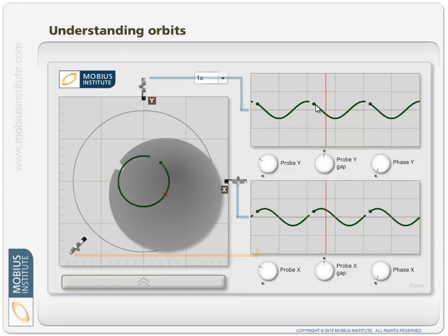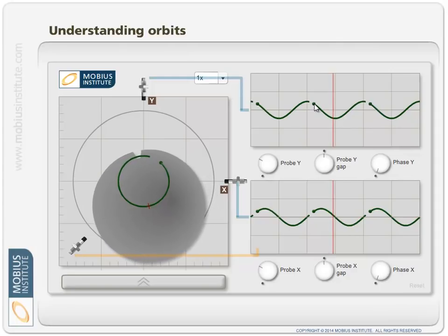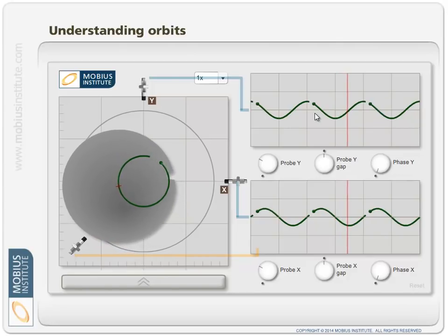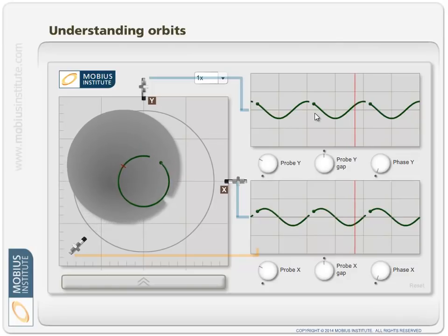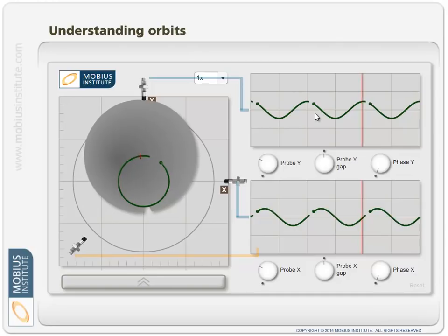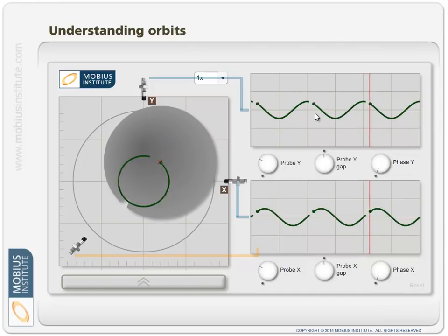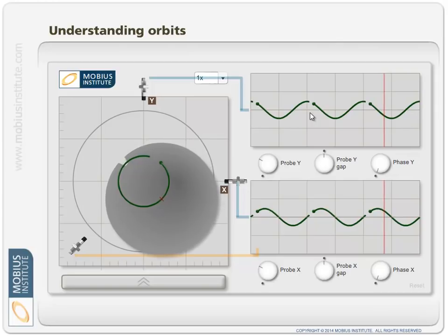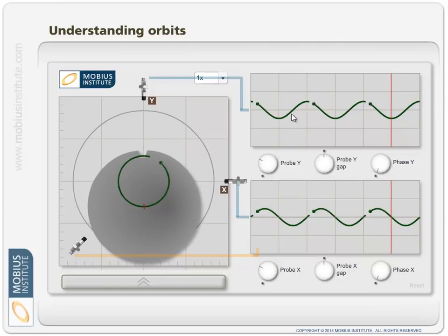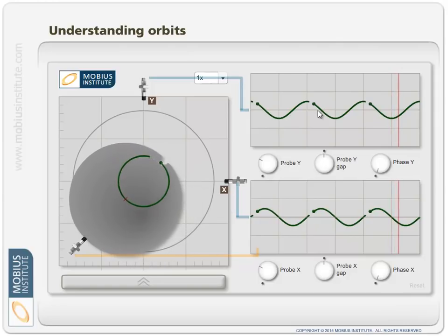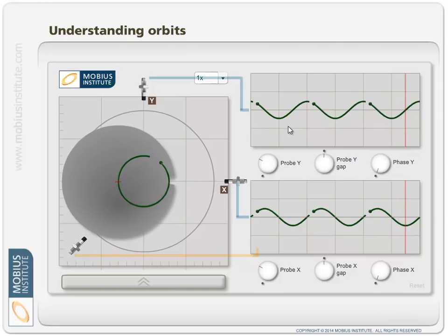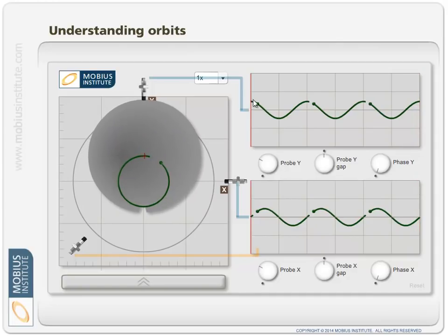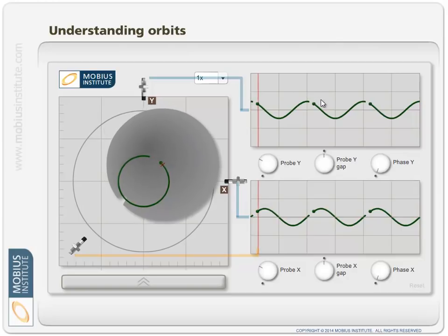It used to be done with oscilloscopes, long story, but here when you look at a time waveform or an orbit with Bently Nevada systems and Emerson systems and these sorts of systems, the bright spot represents the point at which the keyway, or whatever the reference is, goes past your keyphasor. In this case, you can see there's a blank spot before it, and that's by convention now. It's regardless of whether this is an inclusion or a protrusion. Standard convention these days is that we'll go blank, bright with forward precession. So we are rotating in a clockwise direction. The motion is clockwise, and therefore if we follow this waveform, we see blank, bright.